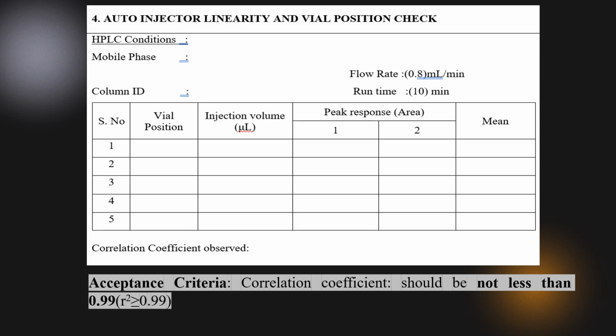You're going to see the linearity of the injection volume. So you're going to set it to 5, then 10, then 20. So you should get a linear graph when you're doing this. And you also need to check the vial position. So you're going to keep vials at different positions, and you're going to check that whatever command you're giving to the instrument, it's injecting that particular sample. So the acceptance criteria for this is the correlation coefficient should not be less than 0.99.